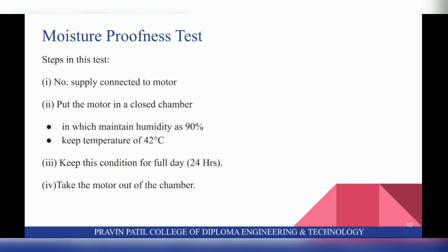Next is the moisture proofness test. Steps in this test are: no supply connected to motor, put the motor in a closed chamber in which maintain humidity as 90%, keep temperature of 42 degrees Celsius, keep this condition for full day, that is 24 hours, take the motor out of the chamber.